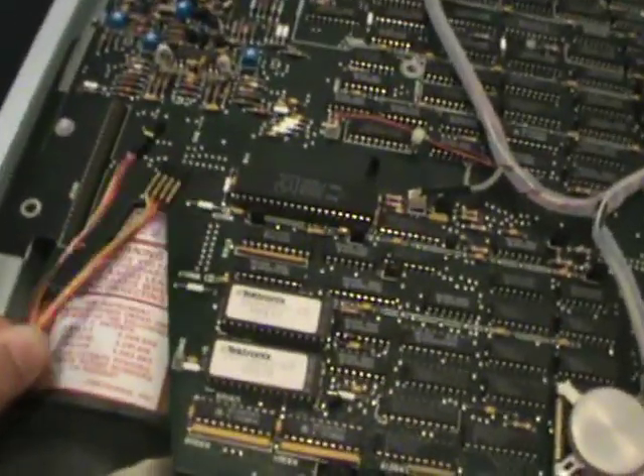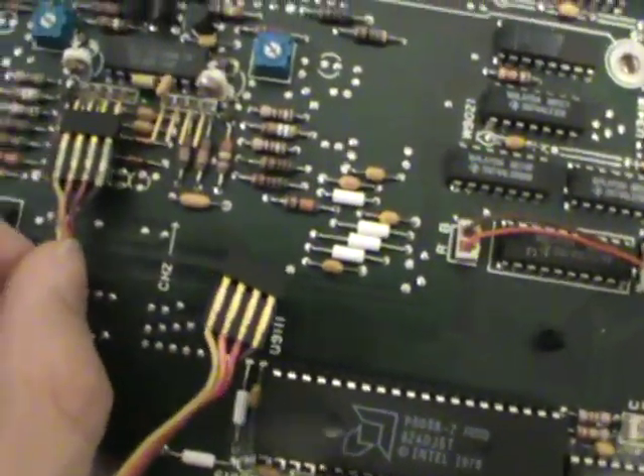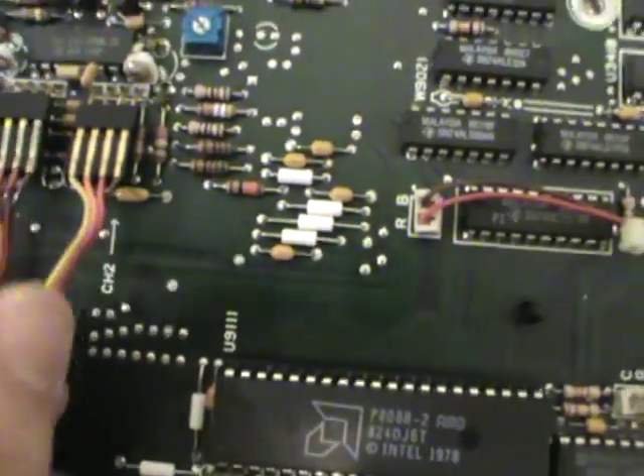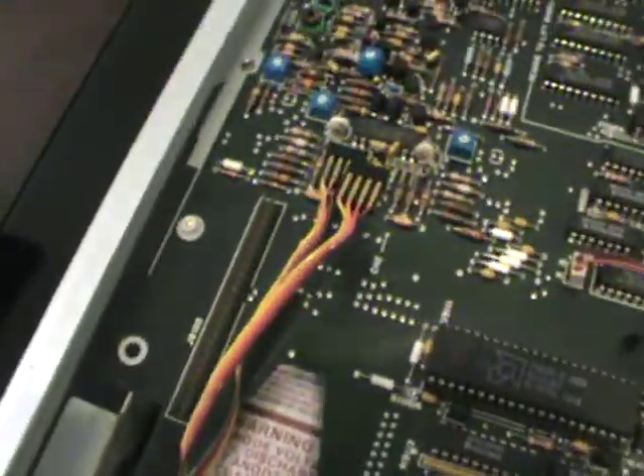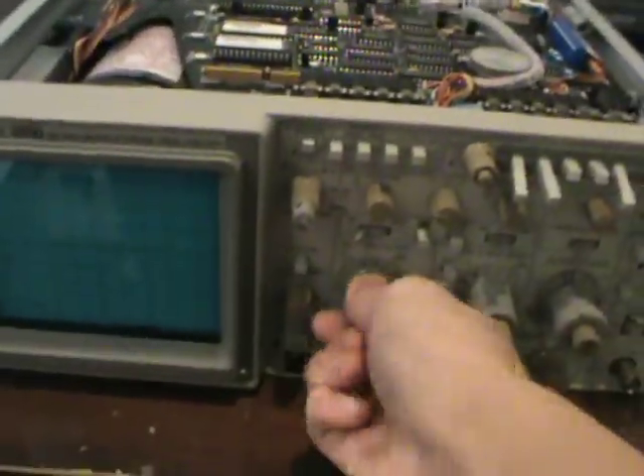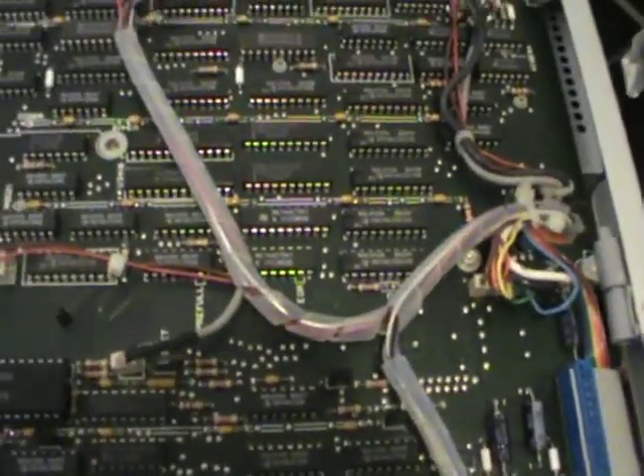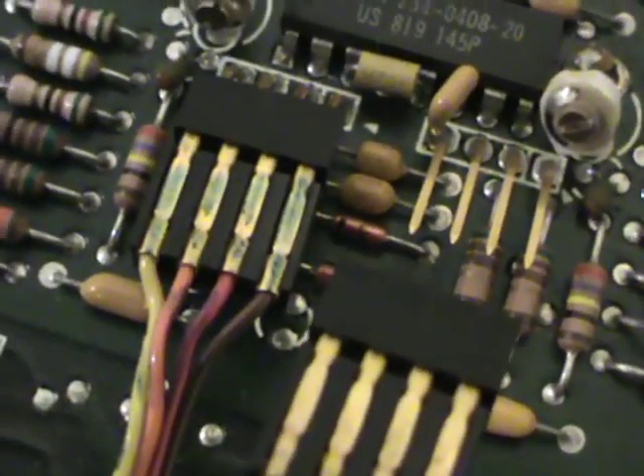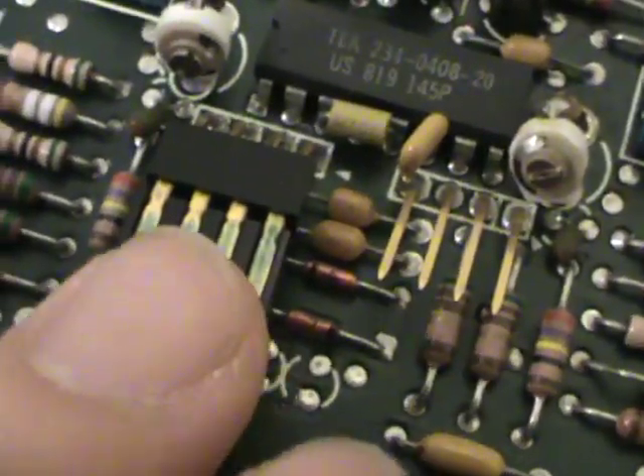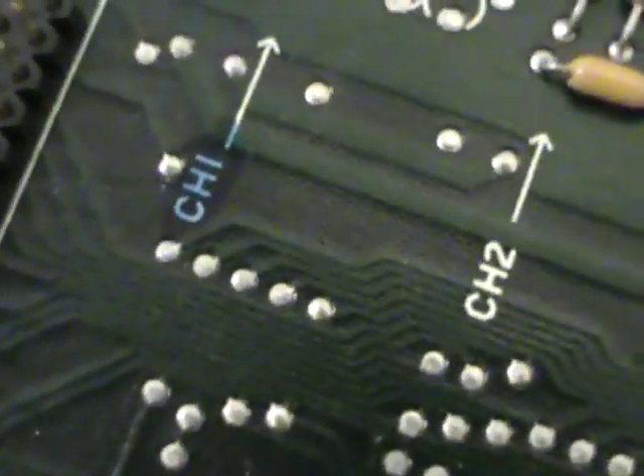We have that acquisition board on top here. And these two connectors are what I want to talk about. These two go right over here into these. And you do not want to mess these up. You do not want to put this one accidentally into this one right here. Because what that will do is mess up the digital controls up here and the readout parts. So channel 1 and 2 will have some switched functions and it will all be messy. So what I want to do is maybe mark the connectors. Here you can see I made this one blue here. And under it highlighted the channel 1 as blue. So I will never get those mixed up.